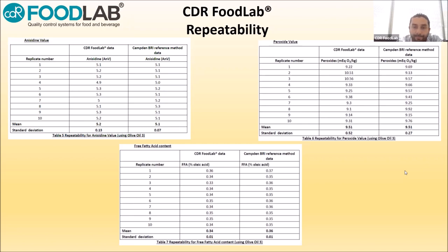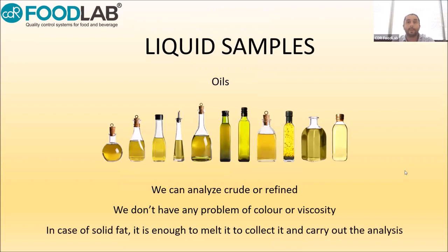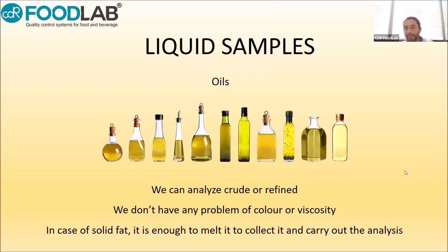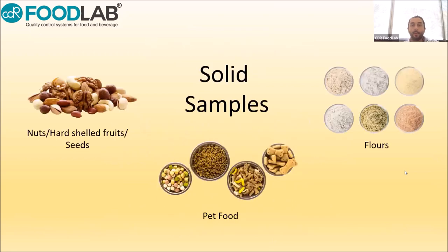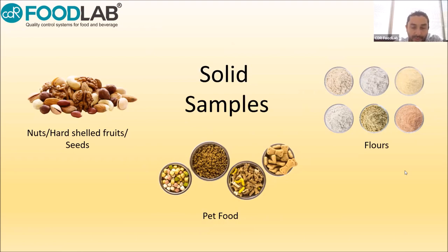For liquid samples, we can work on all kinds of oil or fat, crude or refined — no problem with color or viscosity. In case of solid fat, it is enough to melt it, collect the sample, and carry out the analysis. For solid samples such as nuts, shell fruits, seeds, snacks, pet food, or flour, we need to perform a small sample treatment to extract the oil. We will see a few examples of these extraction procedures.